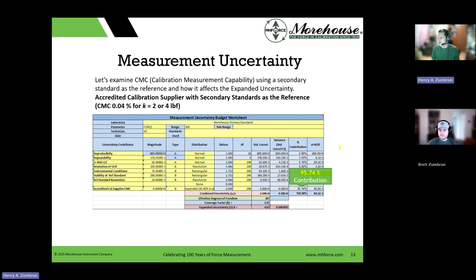In actuality, what's going to happen is over here, the repeatability is going to get a little bit worse, because you just can't control the force like you can with a primary standard. You're just sitting the weights on something, and they do oscillate, but it's very low amounts of drift if the indicators are stable and have good filtering. When you have that other machine, it's harder to control, so the repeatability goes up a bit. But if we're looking at this, we do the calibration with our deadweight primary standards. These overall contributors, nice graph over here. We do that versus somebody else doing it. Overall contribution looks pretty close, right, Brett?